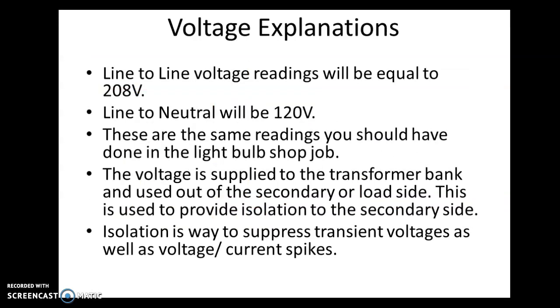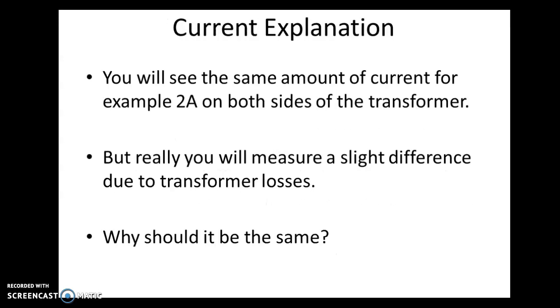A couple more explanations. So the line-to-line voltage reading should be equal to 208 volts. The line to neutral should be 120 volts. These are the same readings you should have taken in the light bulb shop job previously. The voltage is supplied to the transformer bank and used out on the secondary side, also known as the load side. This is used to provide isolation to the secondary side. Why do we do that? Isolation allows us to suppress transient voltages as well as voltage or current spikes.